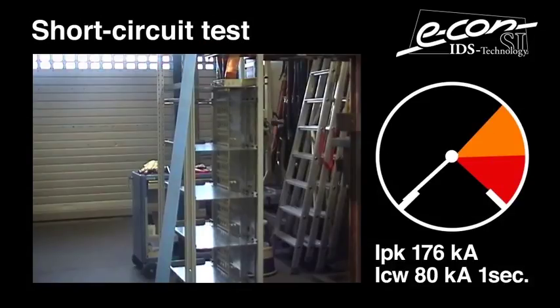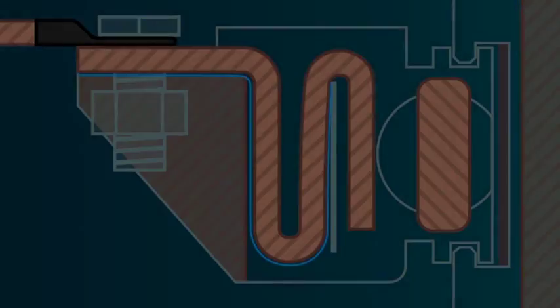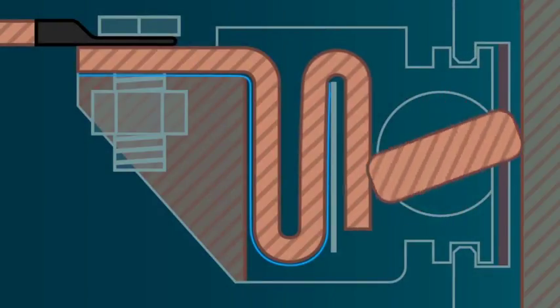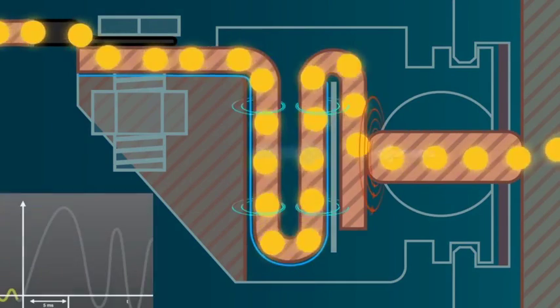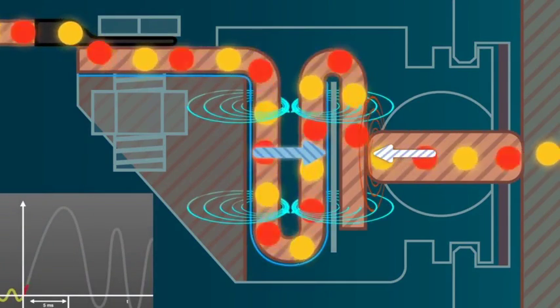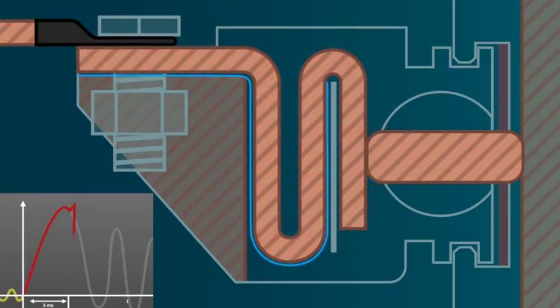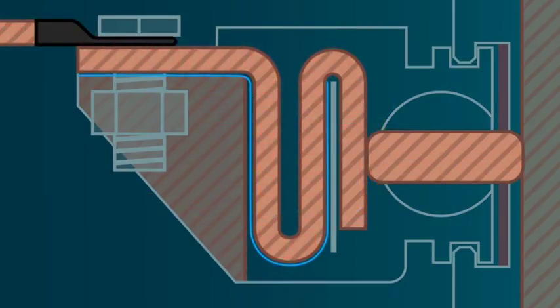The pressure contact works because the contact can slide horizontally over the surface of the copper bar. Geometry and dimensions of this pressure contact ensure that the magnetic field within the u-shaped conductor generates a higher force than the opposite repulsive contact force caused by the electromagnetic contraction.